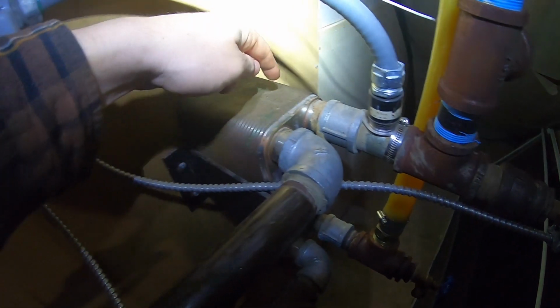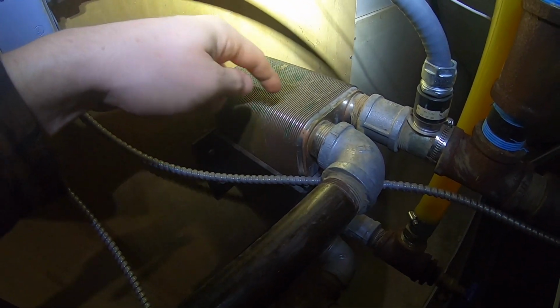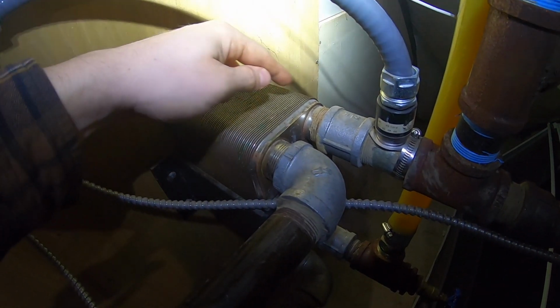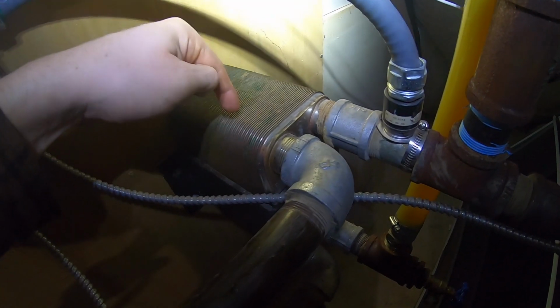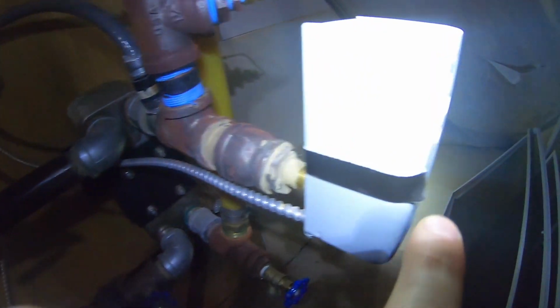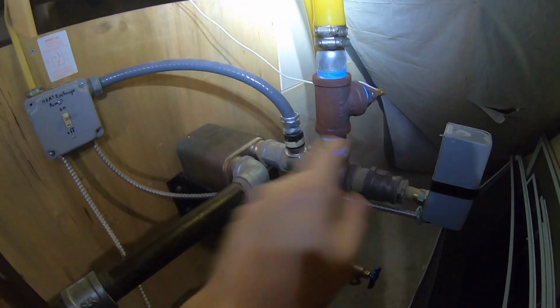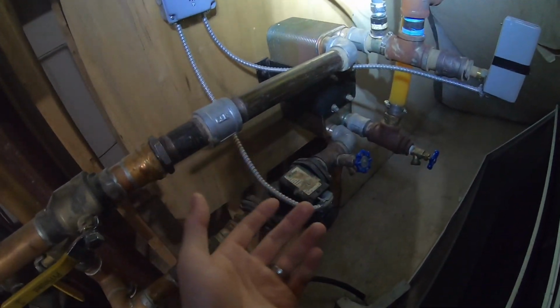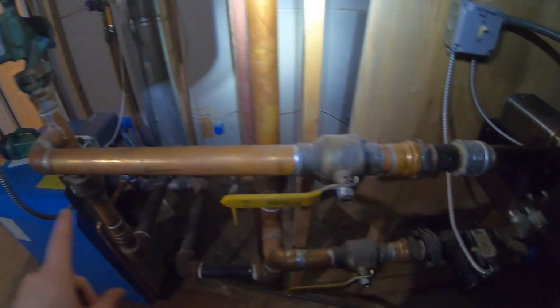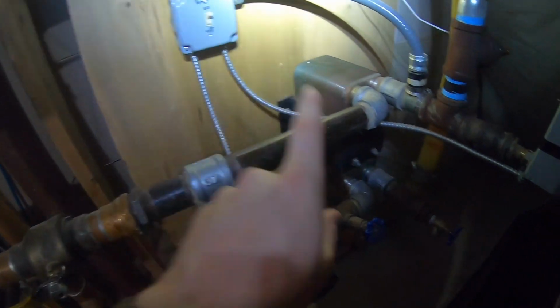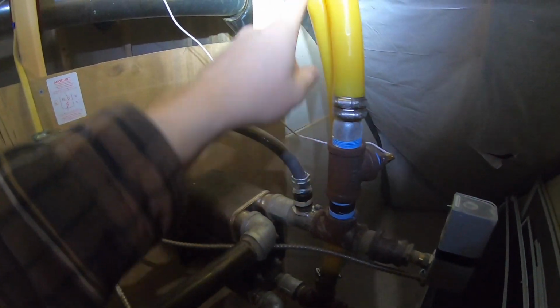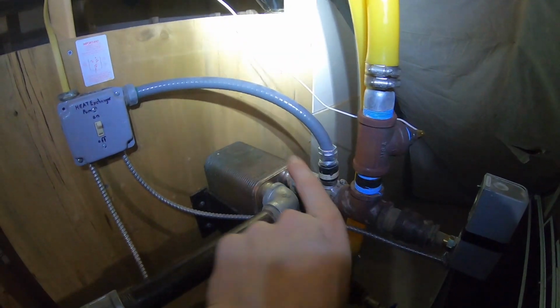Instead of going from hot to cold, this is going to be your house water. Instead of going from the outdoor wood boiler, 170, 180 degree water, from right to left, now it's going left to right. So it's basically set at 130, and when this pump here senses that the water coming in is 130, it will automatically kick on the oil and reverse the polarity, I don't know if there's a better term for it. Then it will start cycling water heated by our oil furnace through the heat exchanger this way. This feed and return constantly makes a loop, as you can see, through the right side of that heat exchanger.